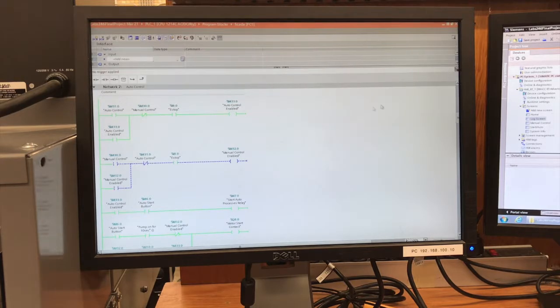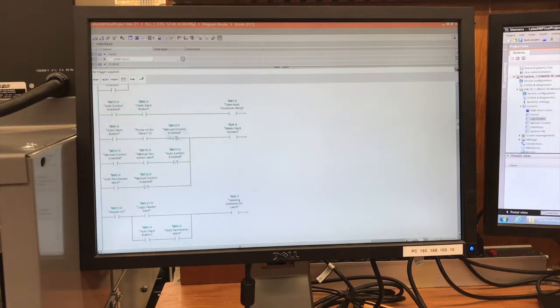So this is showing that the system is currently in auto control. It has an e-stop built into all of these auto control settings, or manual control, so that if you hit the e-stop, every system shuts down. This is the auto processing area, so it has the auto start button before it starts the auto processes, and it also has the motor start contact and everything latched, dependent on its control. That's why there's the 3 separate lines.